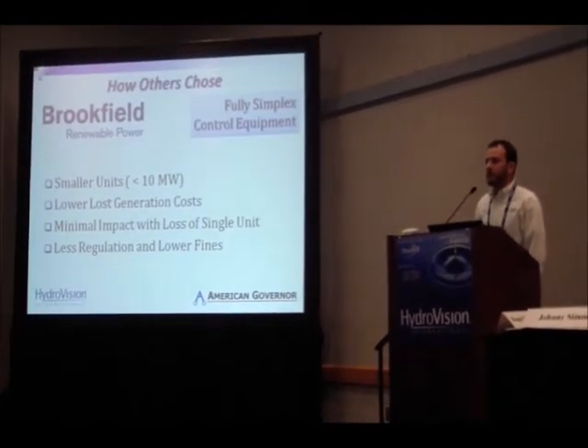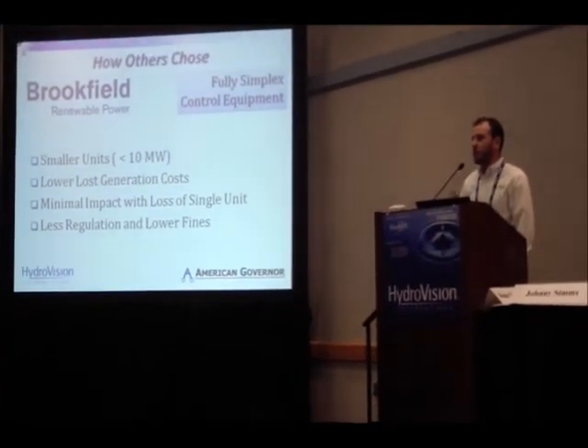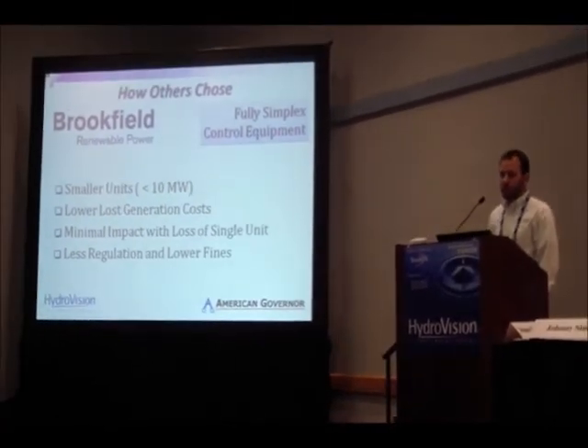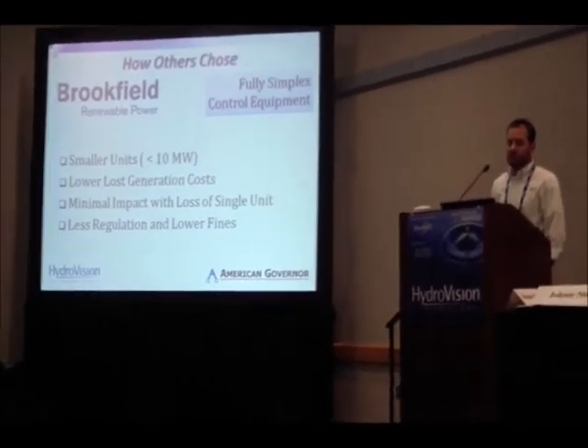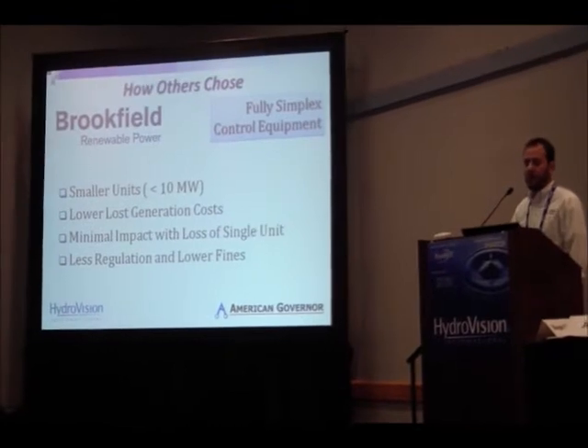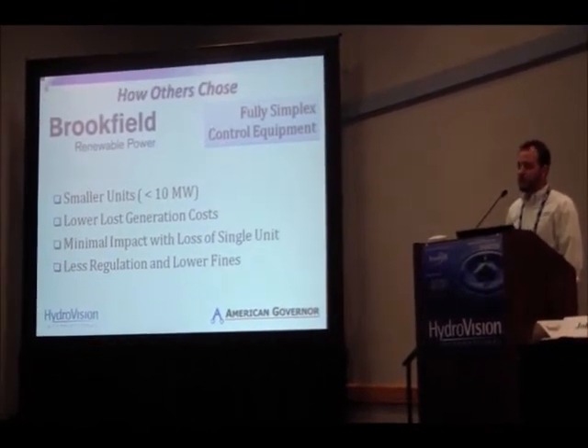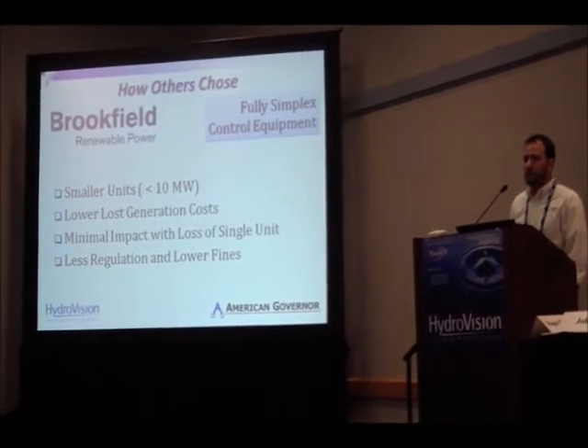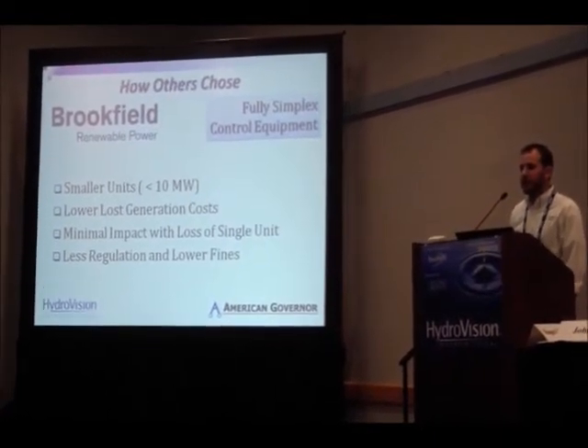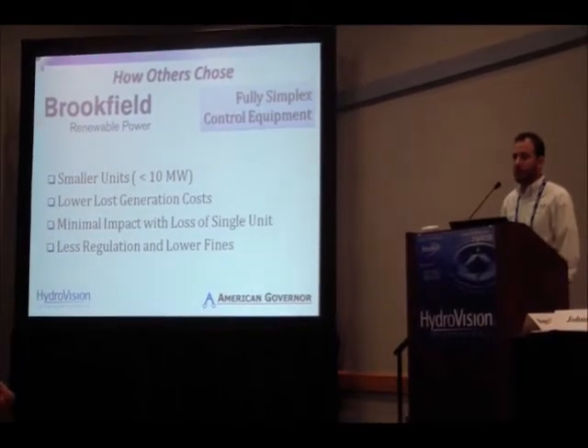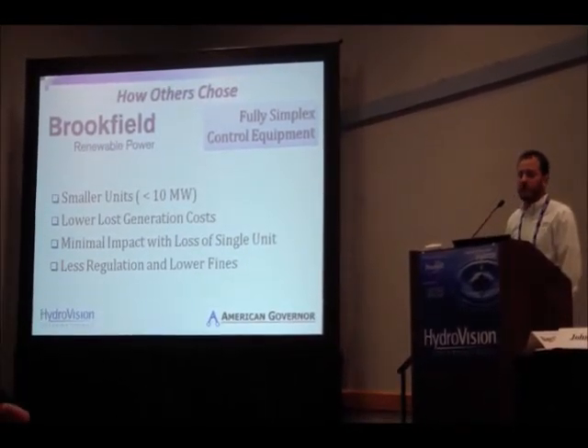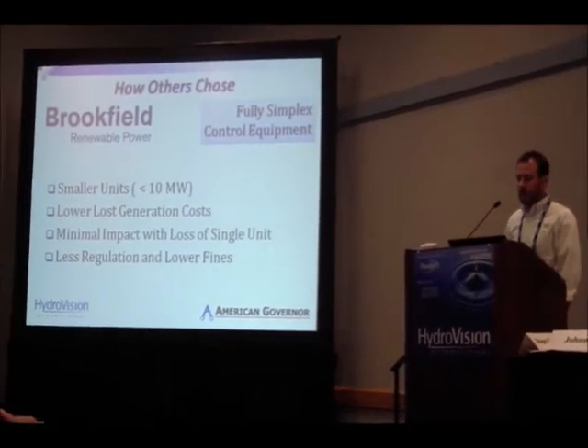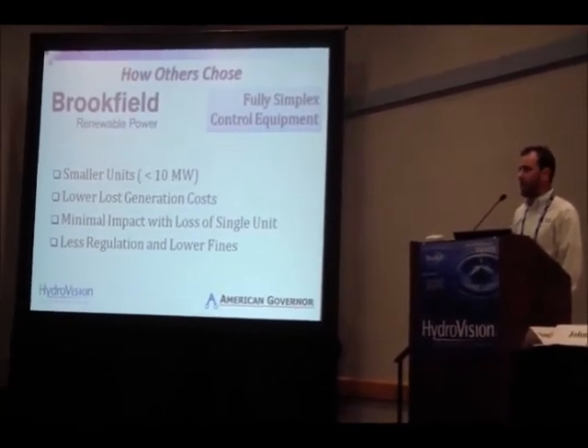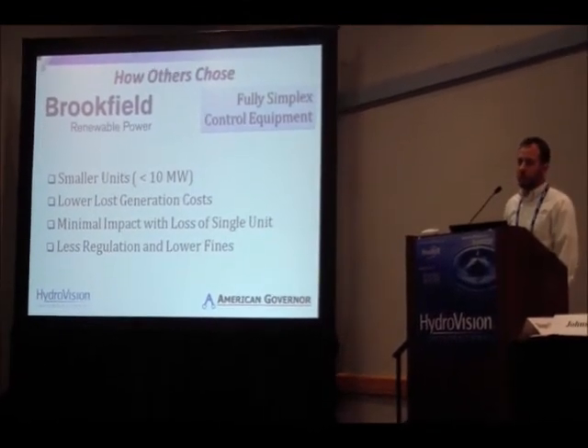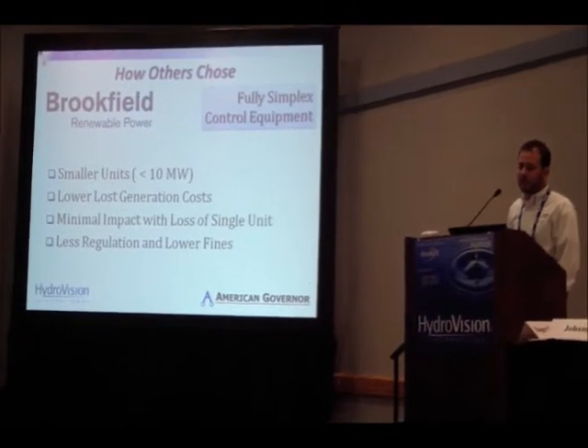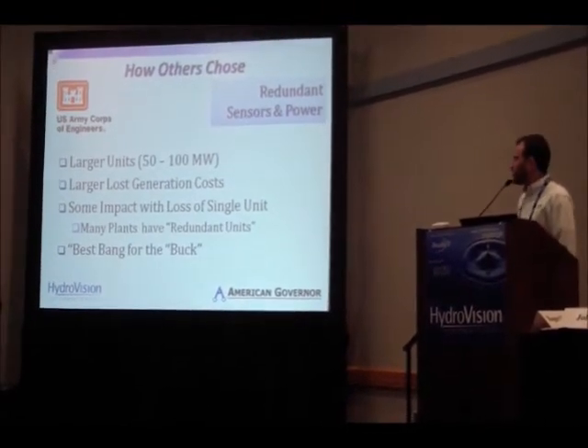Brookfield Renewable Power has many hydro installations in New York and Maine. Many of them are under 10 megawatts, small units. So they chose fully simplex equipment. 1 power supply, 1 controller, 1 output. At under 10 megawatts, their lost generation costs are less. If their unit goes down, they're relying on that energy, but they have 40 other units in a 20-mile radius that are also generating. So your cost for a single loss is less. And there's less impact of that loss. These units are regulated less, so there's lower fines. They're not required to pass the same quantities of water. So failure is tolerable.